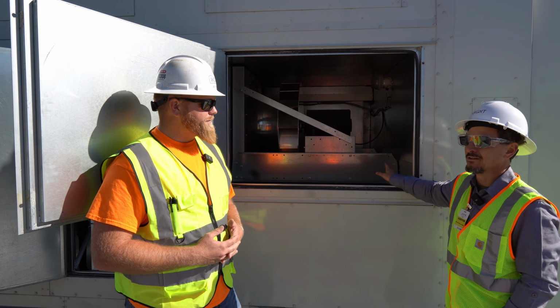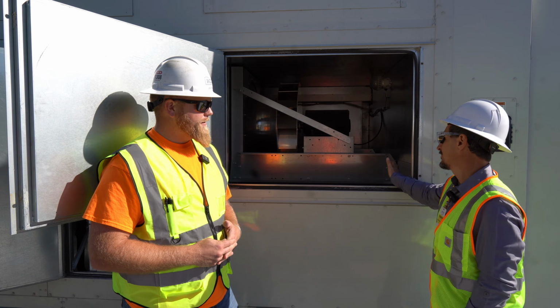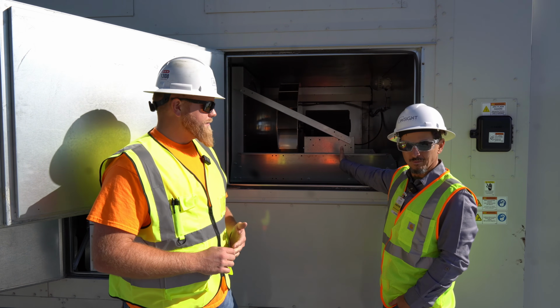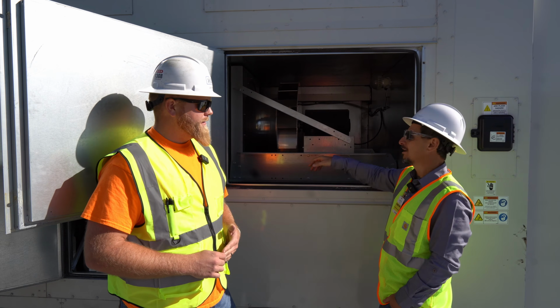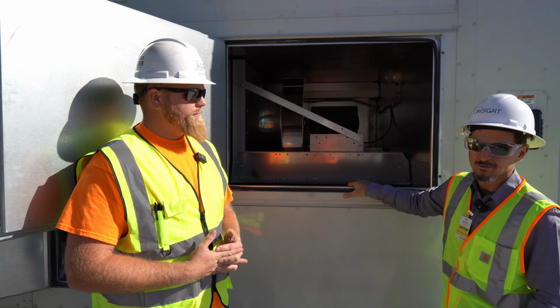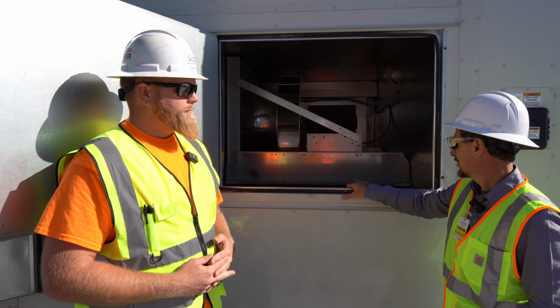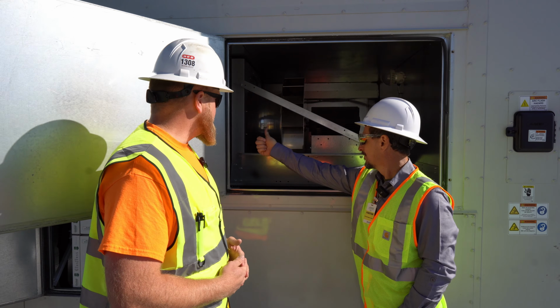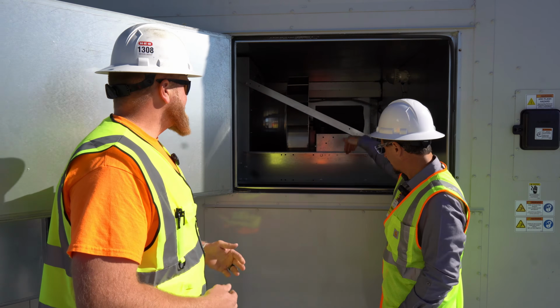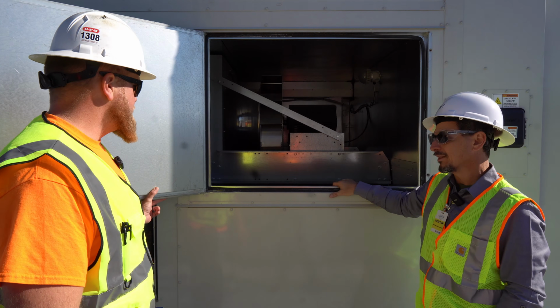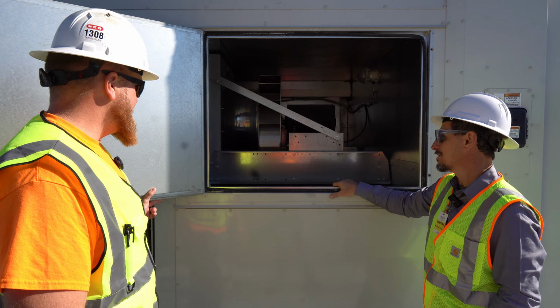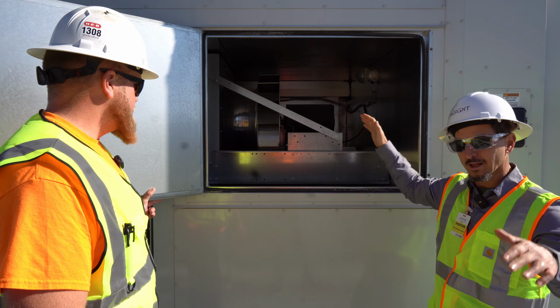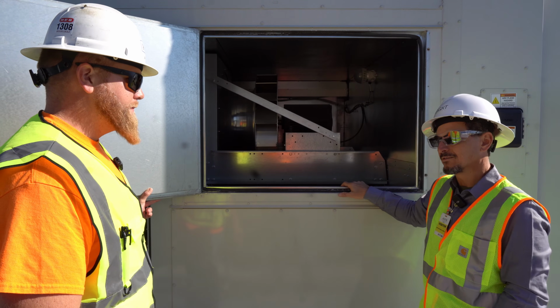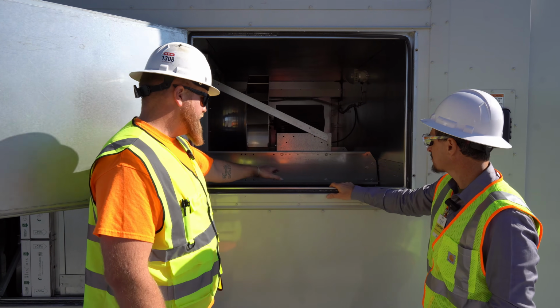And this will modulate. For people who are watching who don't know, this is what's called a direct drive, because there's no belt. Yep. It's a BI plenum fan. That has to do with the way the blades are shaped. The air is coming from this way, going over the motor and blowing down into the supply plenum here. But this is kind of a unique application because they're all operating in unison. So we do have one safety feature inside of here.